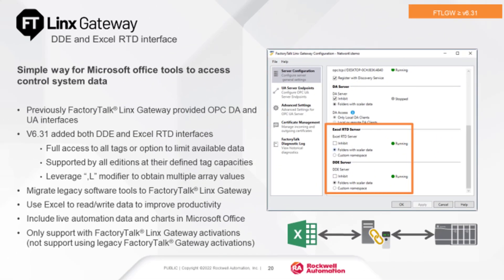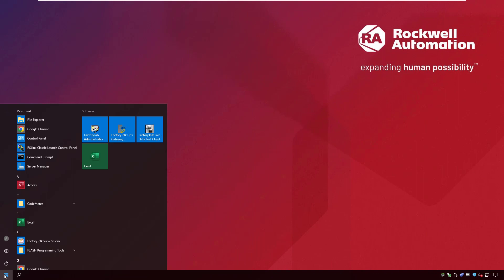There are two options for Excel RTD and DDE: Folders with Scalar and Custom Namespace. Folder with Scalar uploads the entire namespace from the data servers. Custom Namespace only uploads tags listed in the custom configuration. The number of tags in the namespace will affect the FactoryTalk Linx Gateway activation.